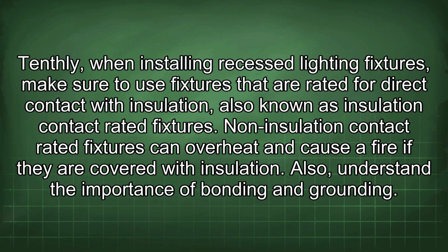Tenthly, when installing recessed lighting fixtures, make sure to use fixtures that are rated for direct contact with insulation, also known as insulation contact rated fixtures. Non-insulation contact rated fixtures can overheat and cause a fire if they are covered with insulation.